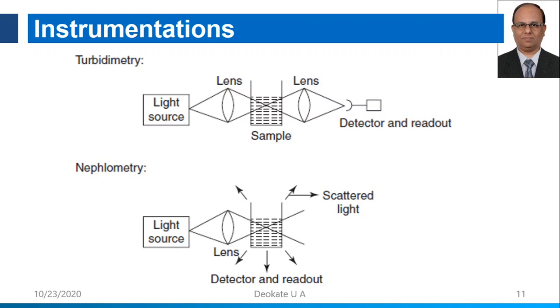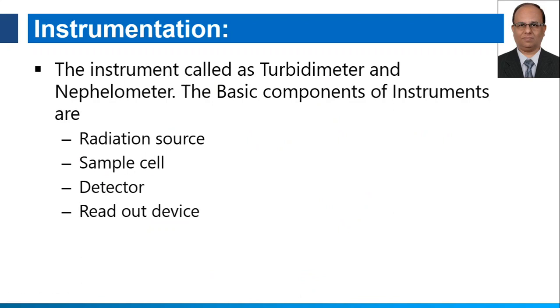Looking at the instrumentation, there are two types of instruments: Turbidometers and Nephelometers. The only difference is in the position of the detector. In the case of Turbidometry, the light source, sample, and detector are placed in the same path at 180 degrees. Whereas in the case of Nephelometry, the light source and the detectors are at right angles to each other, because we are measuring the scattered light. The basic components of the instruments are: radiation source, sample cell, detector, and readout units.